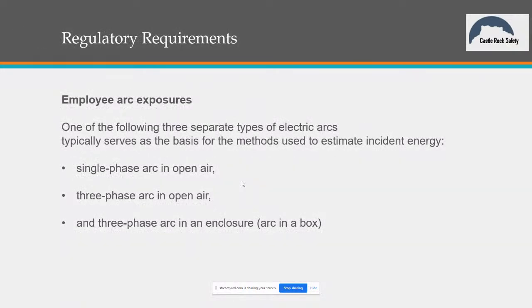Gotcha. Now, here's where it gets a little bit sticky. As you guys know, on the utilization side, we use IEEE 1584, that's where we get our equations to calculate the incident energy. Okay. Right. On the utility side, because of the voltages, most arc flash is considered a single phase event. It's extremely rare, and very difficult to have a 3-phase event, even on a distribution line, and certainly not on transmission.